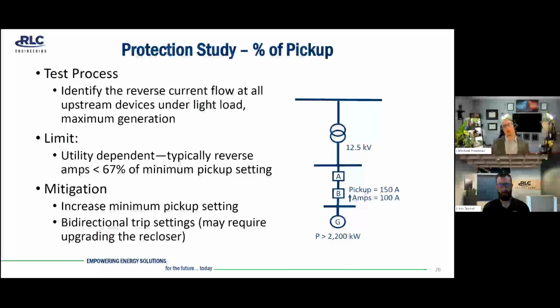Now, percent of pickup is an interesting one, and this is where we see a lot of impacts from DER interconnections. For this, we would look at the reverse current flow at all upstream devices under the maximum generation export scenario, so light load, maximum generation. A typical criteria we see is that the reverse amps flowing through the device should be less than 67% of the minimum pickup.